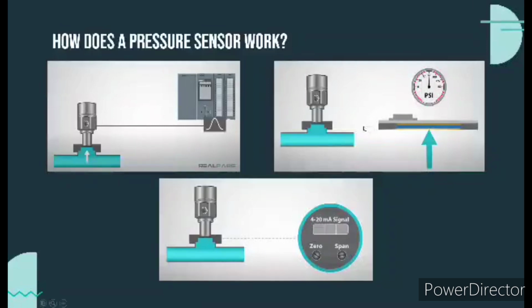Most pressure sensors work off of the piezoelectric effect. This is when a material creates an electric charge in response to stress. This stress is usually pressure but can be twisting, bending, or vibrations. The pressure sensor detects the pressure and can determine the amount of pressure by measuring the electric charge.